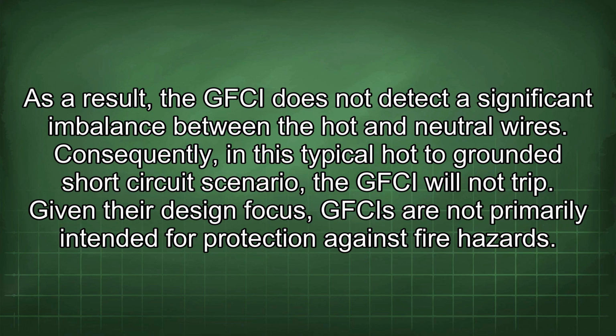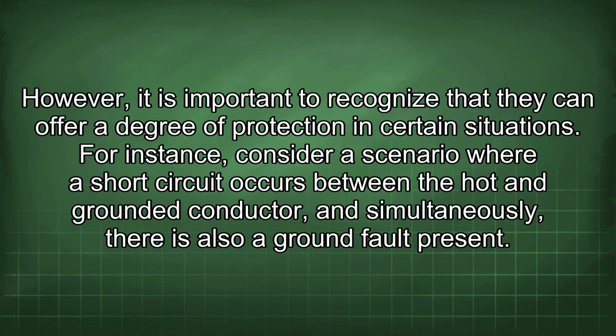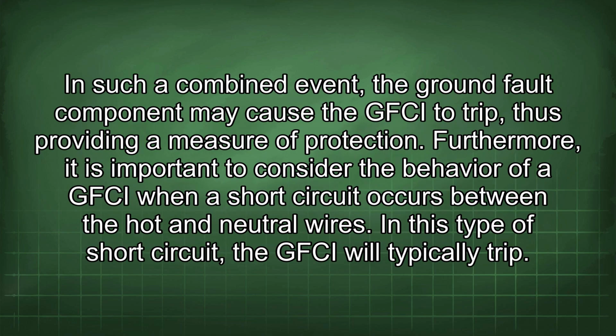Given their design focus, GFCIs are not primarily intended for protection against fire hazards. However, it is important to recognize that they can offer a degree of protection in certain situations. For instance, consider a scenario where a short circuit occurs between the hot and grounded conductor, and simultaneously, there is also a ground fault present.